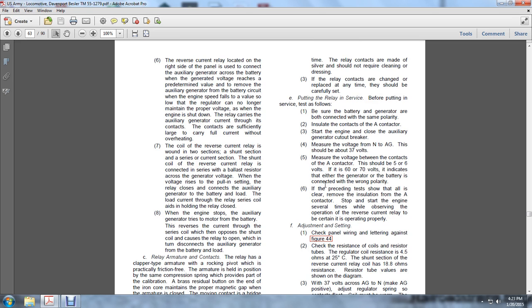7. The reverse current relay is located on the right side of the panel and is used to connect the auxiliary generator across the battery when the generated voltage reaches a predetermined value. It removes the auxiliary generator from the battery circuit when the engine speed falls to a value where the regulator can no longer maintain the proper voltage, as when the engine is shut down.